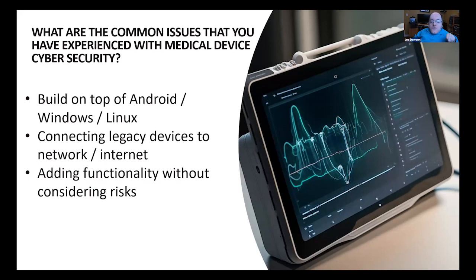And if you hold down, let's say, the power button and the reset button on Android as you're turning the device on, you get into the special bootloader mode, which gets you into a low-level operating system and lets you do massive changes to the device. Those capabilities are built into the operating system. And generally on smartphones and Android tablets, that's a great thing, that you can get into the safe mode and do all these great things in case your device fails. On a medical device, it's a terrible thing, because it allows someone to get in there and change the underlying software on the medical device and get in before your software even starts, and allows them to make some really bad security changes to the device.